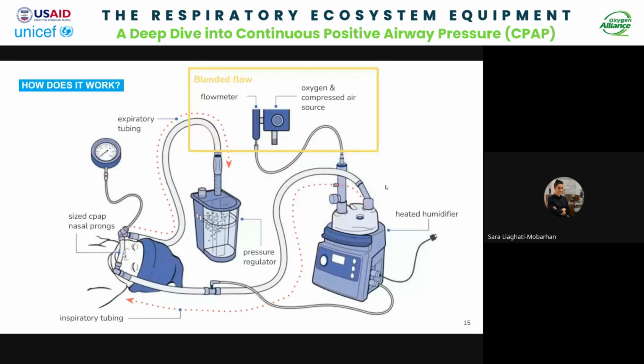These gas sources come into flow meters, and typically there are separate flow meters for both air and oxygen, which can be adjusted to adjust the volume of each of the gases. And the settings on these flow meters determine the proportion of air and oxygen that go into the blended output. And what this means is that you can adjust the percentage of oxygen in the breathing gas mixture that's delivered to the patient, or the FiO2, using the flow rates.